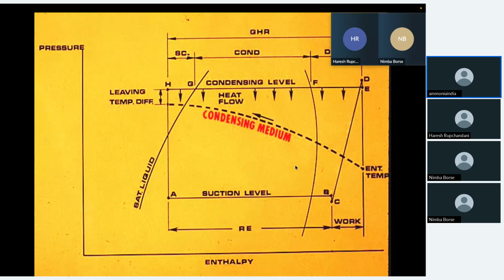One of the plants which was designed, a very big petrochemical plant, the capacity was 100 ton. The gentleman who was designing the plant, a very well-known expert in this field, designed the condenser also for 100 capacity. There were 9 units of 100-ton capacity. It was a very big plant. And what resulted? As soon as we started, the compressor would trip on high discharge pressure, because the condenser was designed wrongly. It was a minus 30 degrees centigrade plant, so the condenser heat rejection becomes nearly 1.6 times more than the evaporating tonnage. So the condenser size should have been 160 tons. Instead of that, it was designed for 100 tons. And unfortunately, that plant never worked and it had to be closed down.